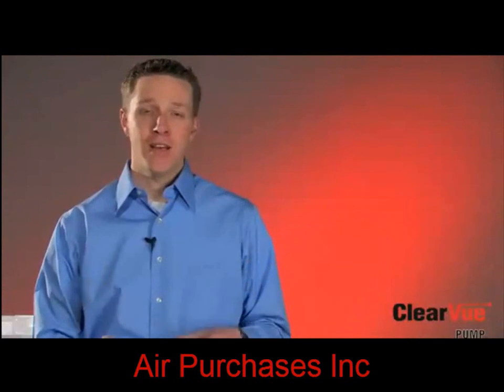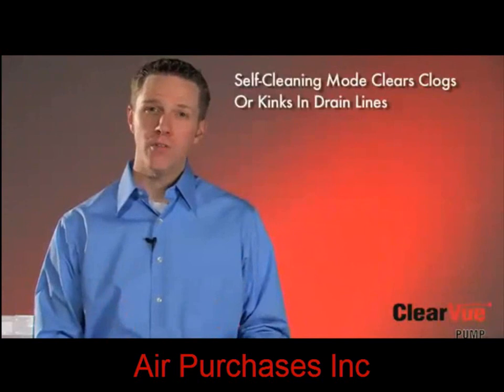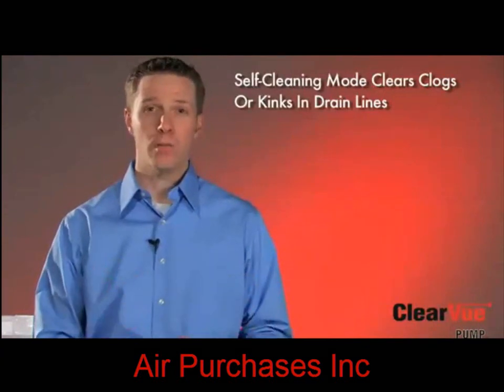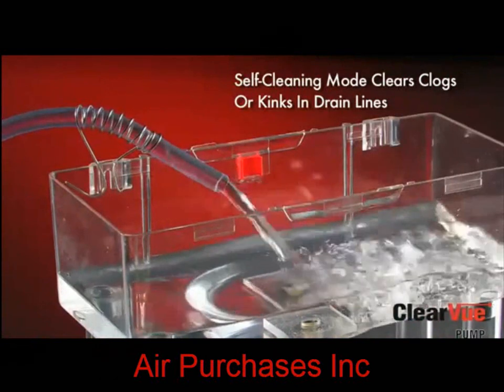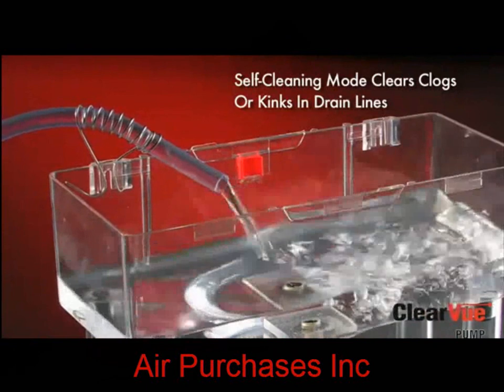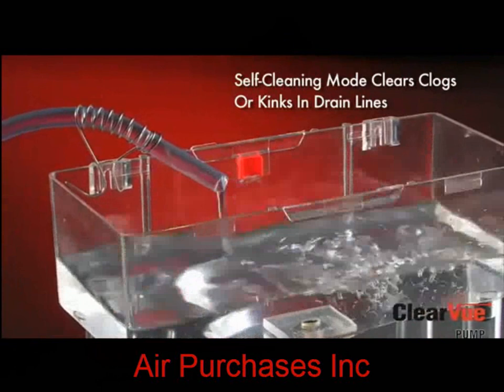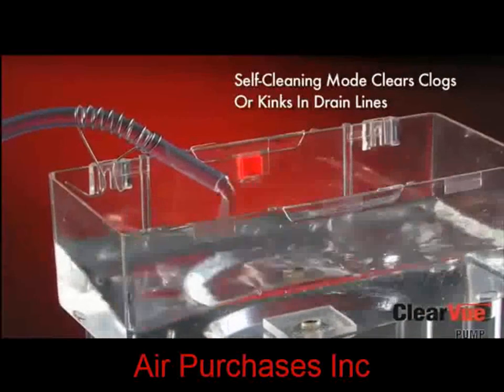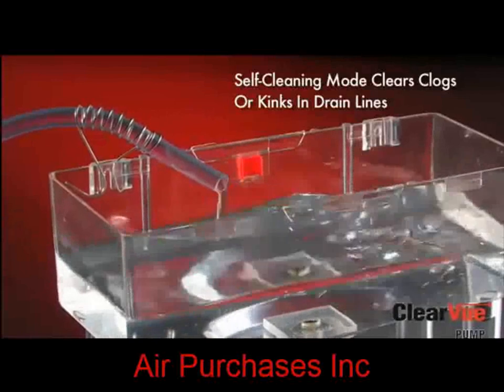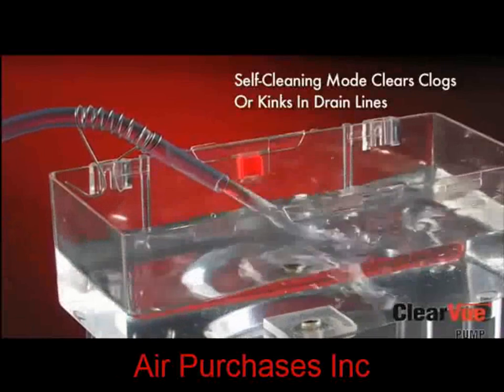Another thing that's happening in alarm condition is that after about a minute of pumping at full speed, ClearVue will go into what we call our self-cleaning mode. The self-cleaning cycle is going to use the water in the tank to send pressure pulses through the line to try to dislodge any clogs or kinks that might have formed. ClearVue has determined that there is a problem and is working to clear the clog and return to normal operation. The pump is trying to get out of that alarm state without a service call. ClearVue is the only pump that fixes itself when it senses a problem.